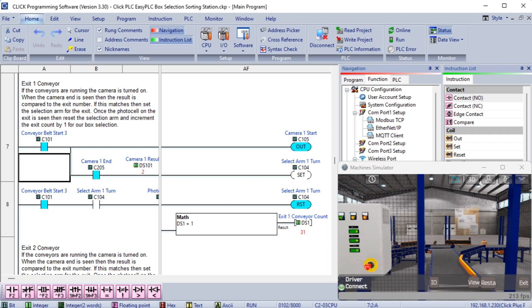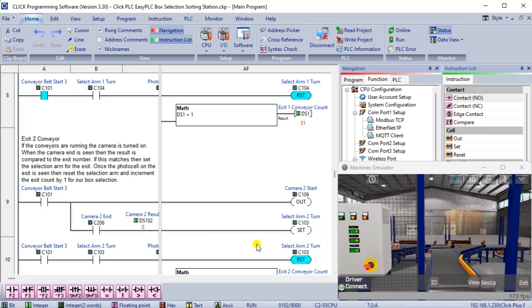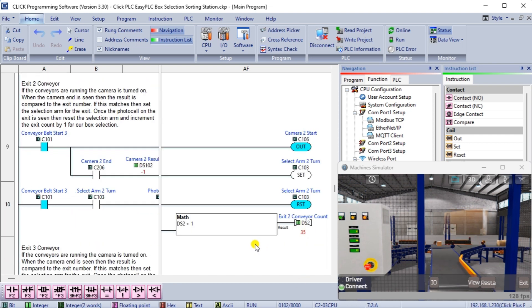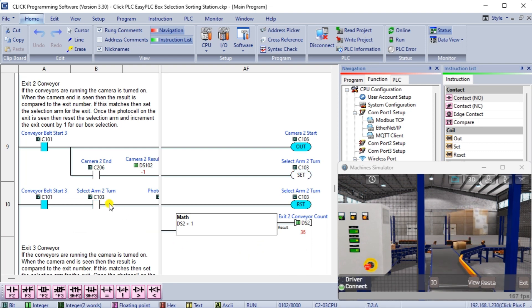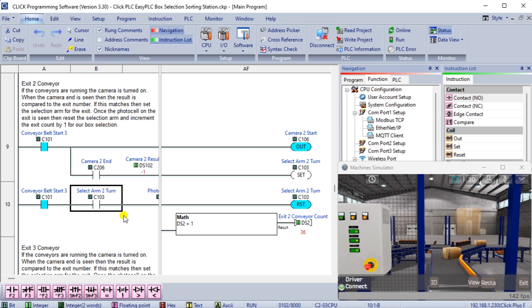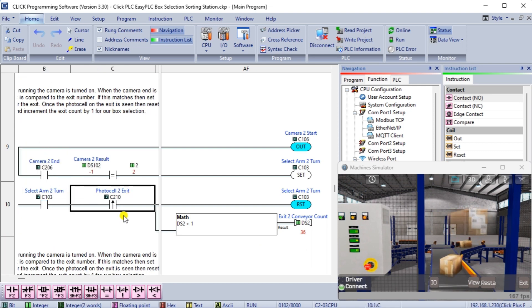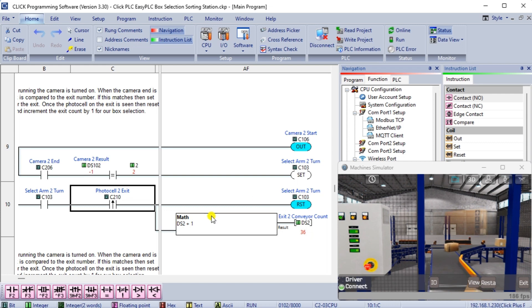Exit 2 conveyor. If the conveyors are running and the camera is turned on, the result is compared to the exit number when the camera end is seen. If this matches, then set the selection arm for the exit. Once the photo cell on the exit is seen, reset the selection arm and increment the exit count by one for our box selection.